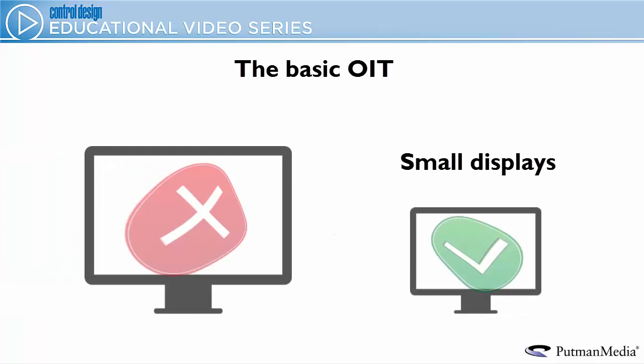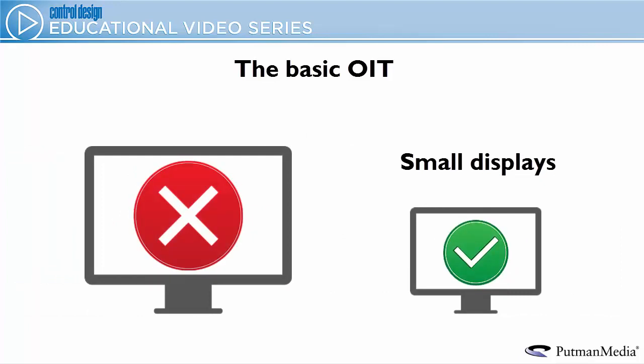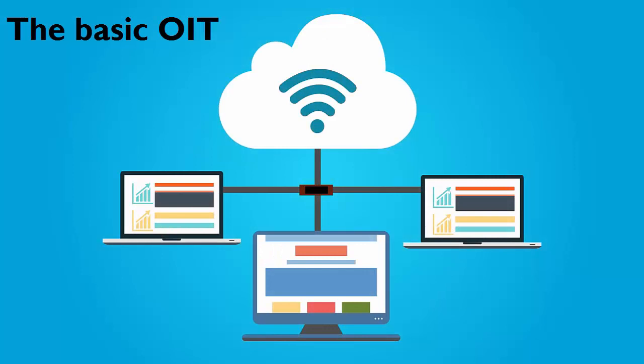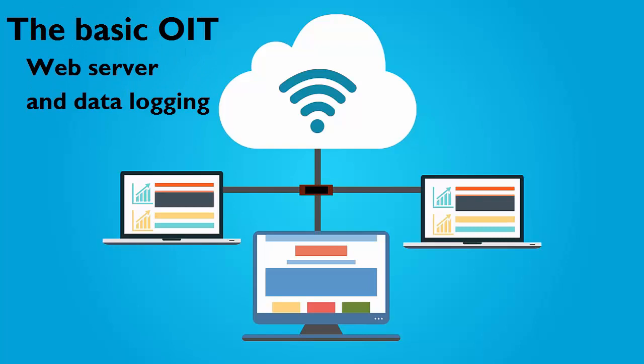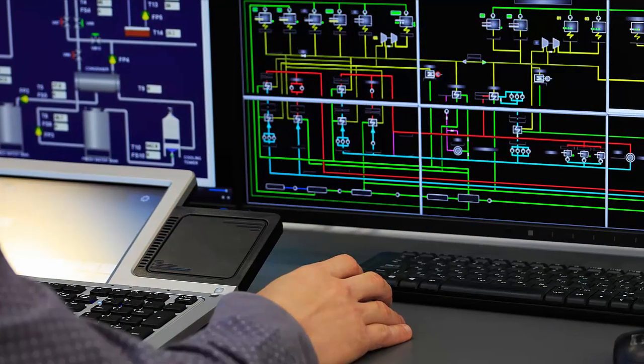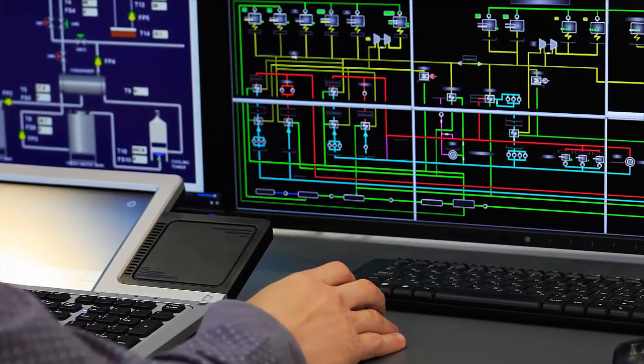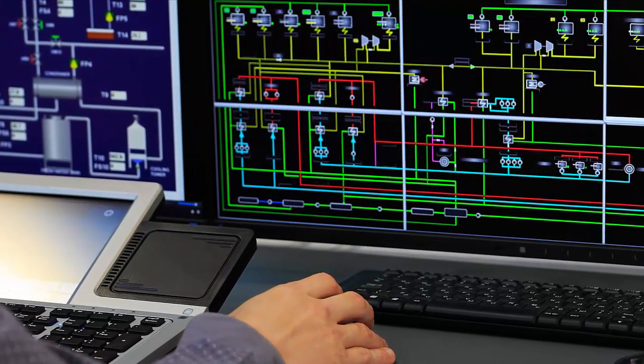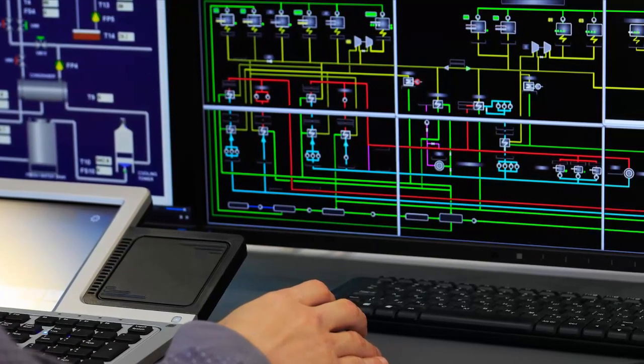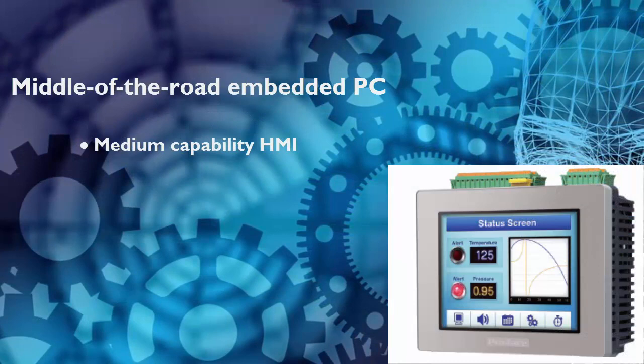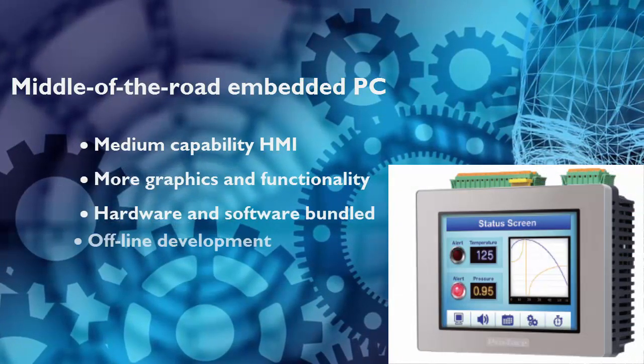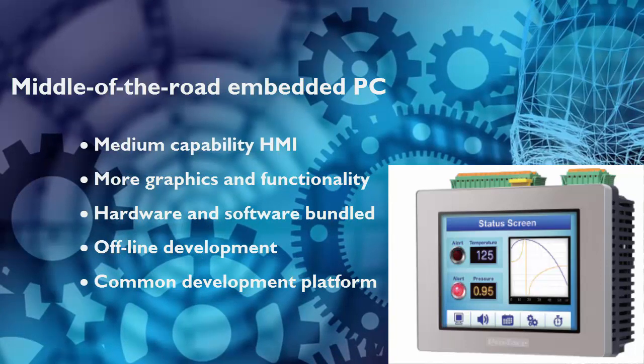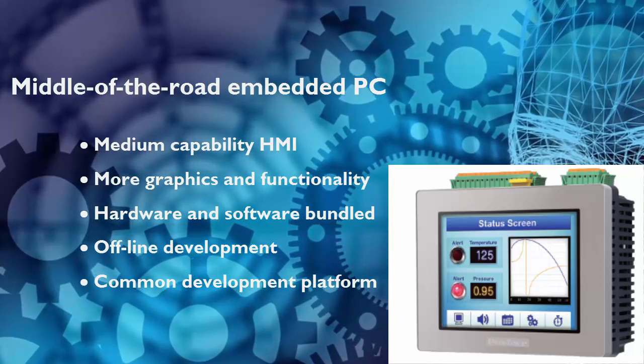It doesn't pay to get a larger display or to spend time on fancy graphics. While the OIT may have limited protocol availability and features, it may still provide a built-in web server, enabling remote access to some of the data, and may even have data logging, but with limited memory to do so. As the machine application requirements move to more graphical screens, buttons, alarm history, recipe functions, trends, and historian functionality — such as those commonly offered by the PLC vendors — HMI software functionality increases. These middle-of-the-road HMIs, usually embedded PCs, still closely tie the HMI hardware and software together.